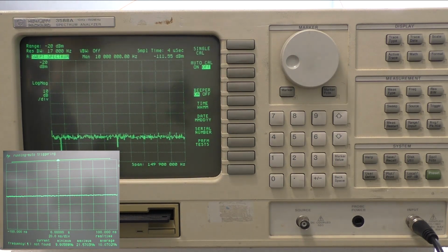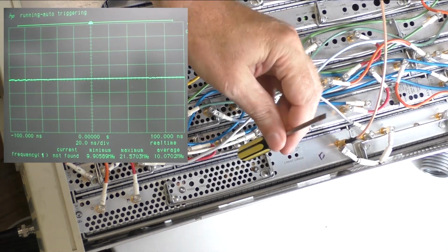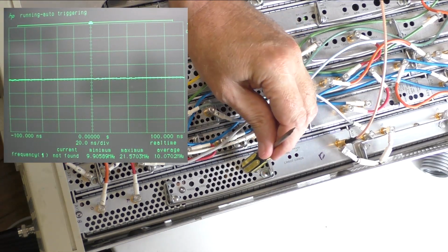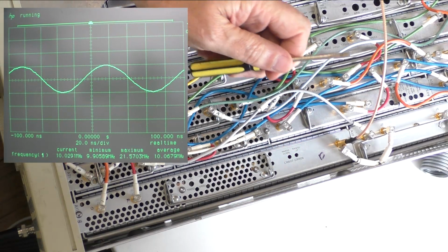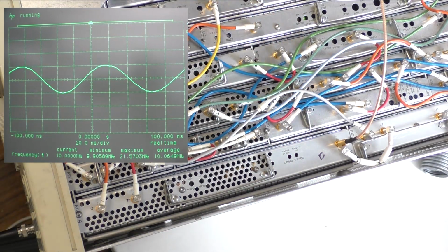Try this a few times. Give the A11 assembly a light tap on top with the handle of a small screwdriver. We see the signal restored on the scope. Why? Our hunch is something mechanical. One of the many relays in the input assembly is failing. By lightly tapping the assembly, the contacts can release or bed properly.